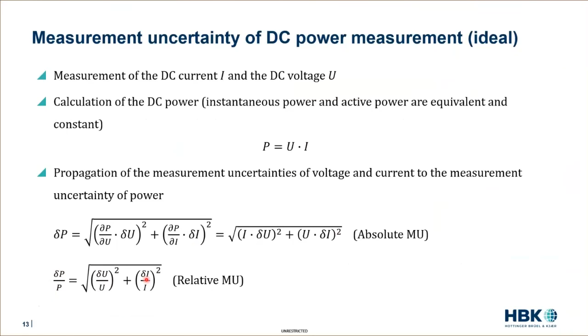And we can now use these formulas and apply them to the active power. In this easy example, the DC active power, which is well known as the product of the DC voltage and the DC current, if you now apply the Gaussian error propagation to that formula, you will see as a result that the relative measurement uncertainty of active power is equal to the squared sum of the relative measurement uncertainty of the voltage and the relative measurement uncertainty of the current. You can also do that for the easy example of ideal sinusoidal AC quantities. Then, of course, the phase shift between voltage and current is also included in the formula.